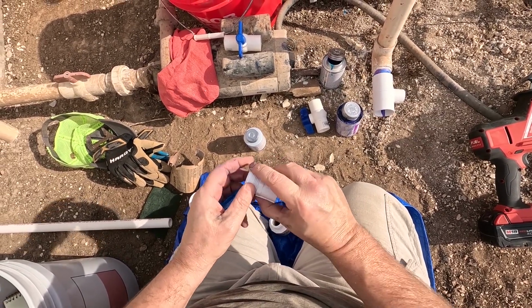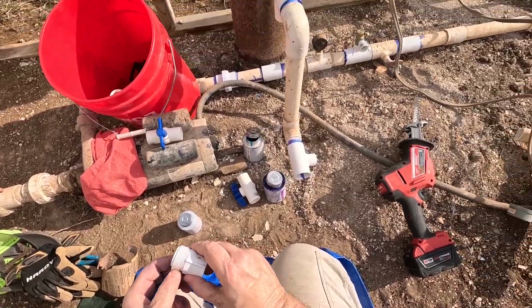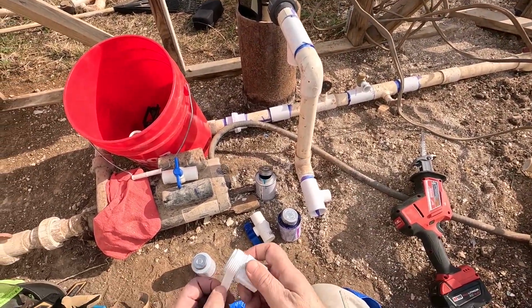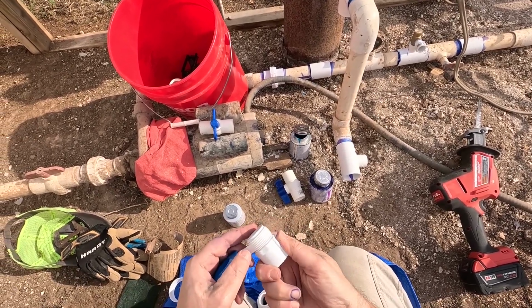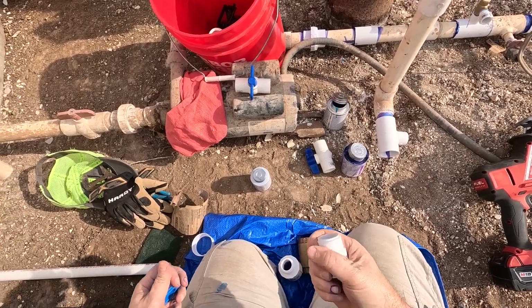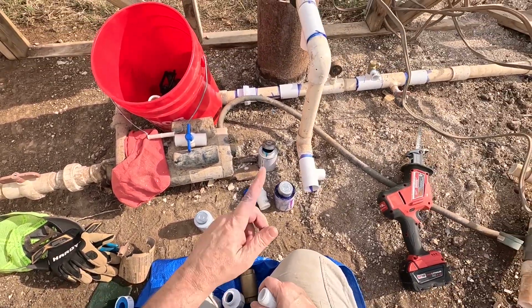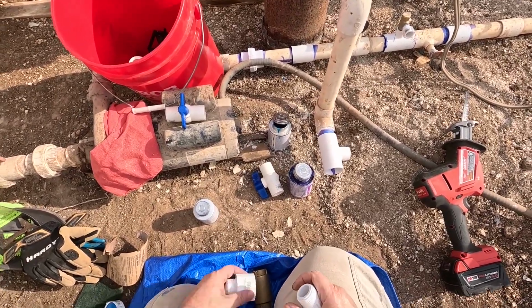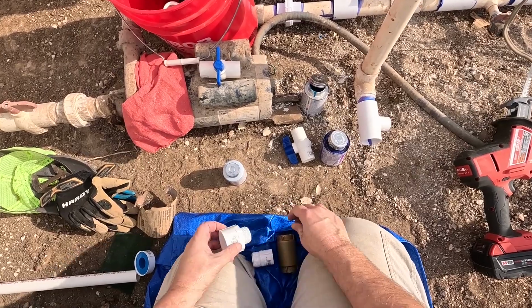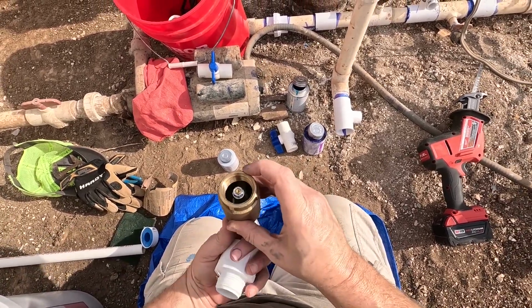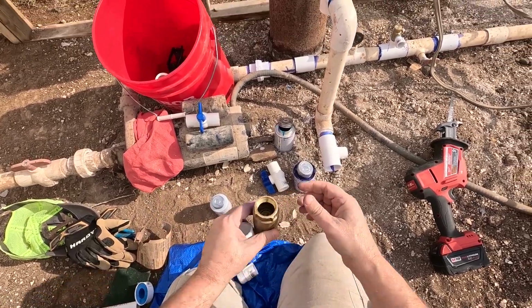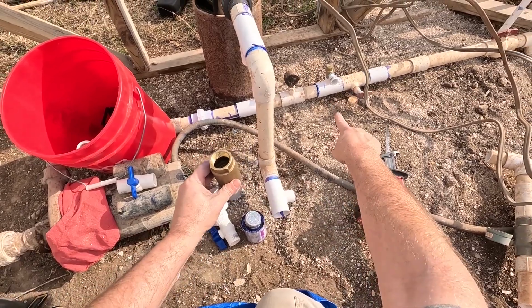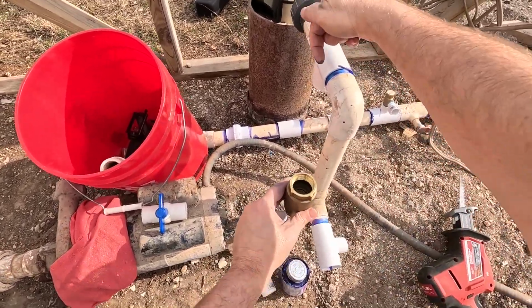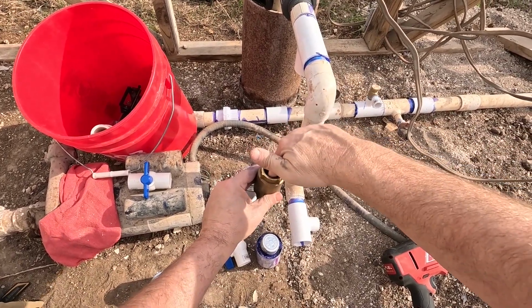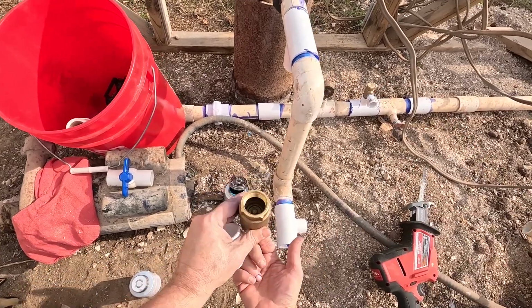The purpose of this is so if the sprinkler system gets overpressured, that valve right there will open and relieve the pressure, letting water out. So when it's letting water out, where do we want that water to go? Well, it's just going to run back into the tank, using the same pipe that the well uses to get water into the tank. The one thing we have to be careful of is when the well comes on, we don't want the water to come down and try to get in here. That's what this is for. The water will come in from the well and go down and can't get in, so it'll just keep going. But if the water comes in from there, it'll come up and open up that valve.